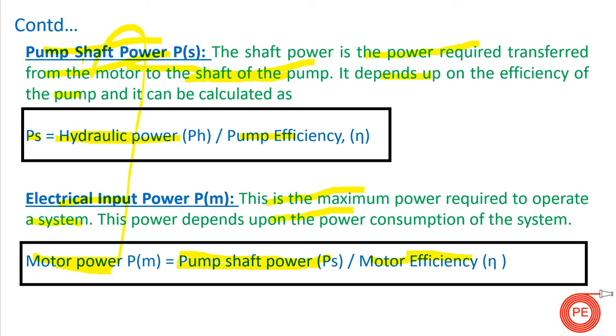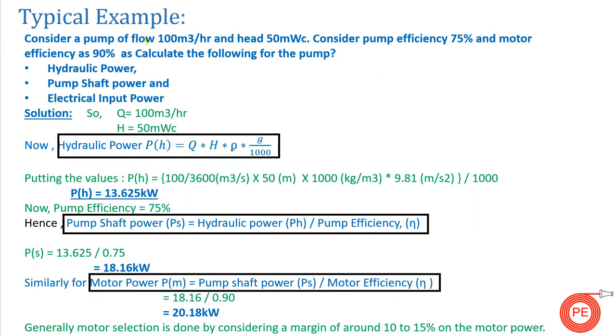Let's see with the help of an example how to calculate all these powers. Consider a pump with a flow of 100 m³/hr and a head of 50 meters water column. Pump efficiency is 75 percent and motor efficiency is 90 percent. Calculate hydraulic power, pump shaft power, and electrical input power. Using the formula P_H = Q × H × ρ × g / 1000, where Q = 100/3600 m³/s, H = 50 m, ρ = 1000 kg/m³, and g = 9.81 m/s², the hydraulic power comes to 13.625 kW.